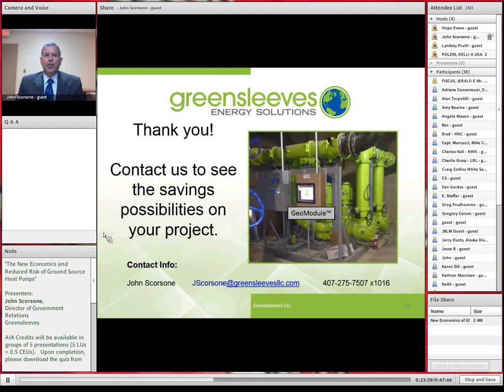So remember earlier, I mentioned bore field design. Traditional ground loop design software lets you do a 1-year design, a 7-year design, a 25-year design. Well, those additional bores you put in to make it last 25 years aren't providing any more capability. They're just allowing for more heat to be put into the ground over time than you take out, and that bore field is heating up. The software accounts for this.